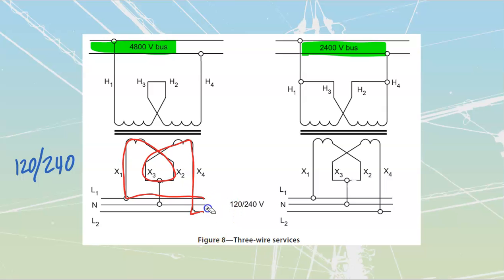Okay, let's talk about what the Canadian Electrical Code requires. We know we've created a neutral point over here. It's an actual true neutral because it counterbalances the currents — if I add the currents inside my neutral, I'll end up with a net of zero, and we'll do some of that addition later on. But anytime I create a neutral, by Canadian Electrical Code Section 10, I must ground that neutral point, placing an actual connection to ground on it. We'll go over grounding and bonding much more in depth later on.